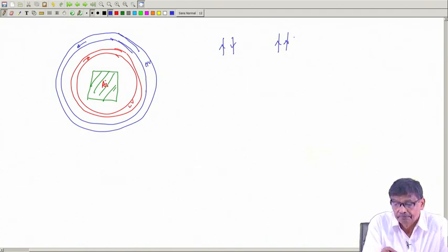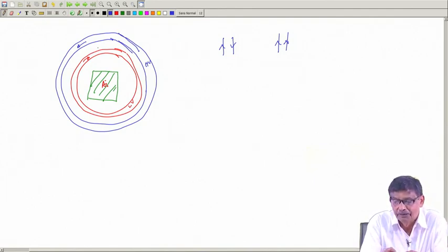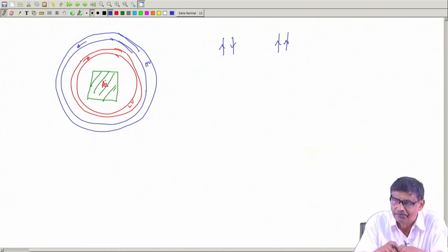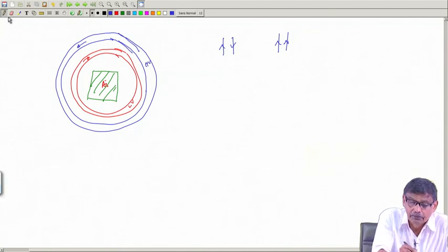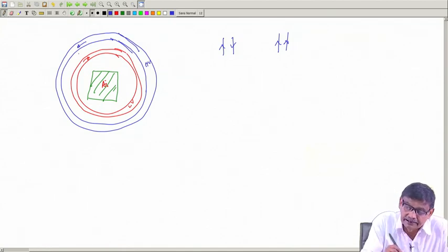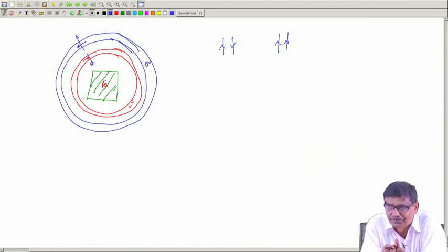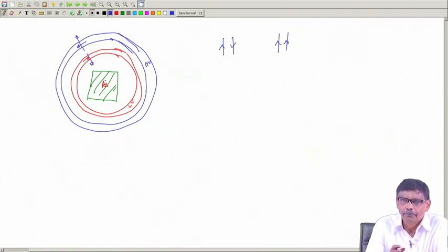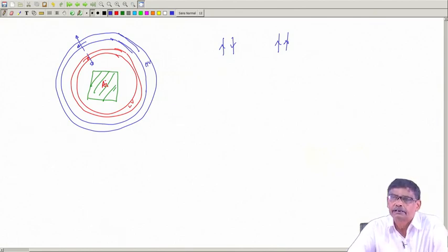That means this LV coil. Now, this LV coil just cannot stay alone. There will be some bobbin sort of thing over which this LV winding is put. So, when normal load current flows, there will be force of repulsion acting, that is, what will be the direction of the force? This way. That is, LV winding will be squeezed towards the core and this will try to go away. So, you have to take proper fixing up of the coil, so that they can withstand that mechanical forces at rated currents at least.